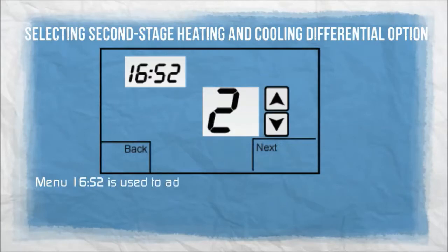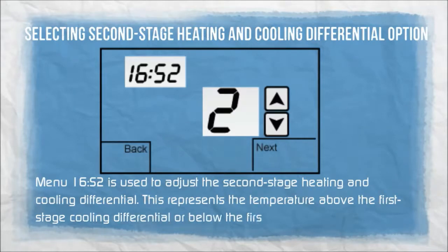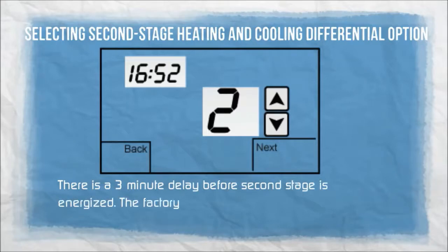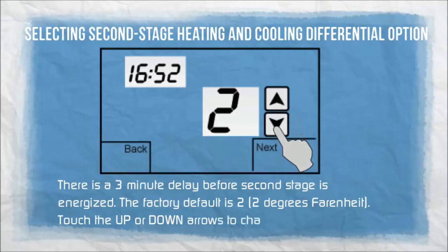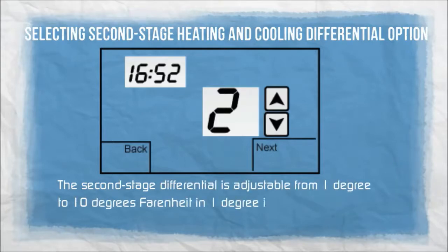Menu 16S2 is used to adjust the second stage heating and cooling differential. This represents the temperature above the first stage cooling differential or below the first stage heating differential when second stage is energized. There is a three-minute delay before second stage is energized. The factory default is two degrees Fahrenheit. The second stage differential is adjustable from one degree to ten degrees Fahrenheit in one degree increments.